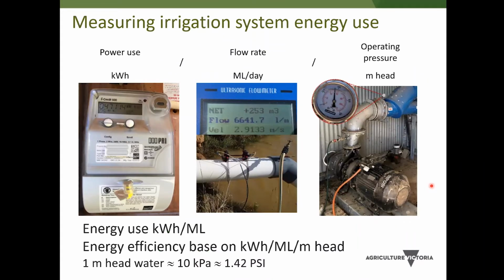Measuring the energy use of a pumping system is actually pretty easy. Most people could easily do it. All we need to do is measure power consumption or diesel consumption over the same time as we measure the amount of water applied. So we need a dedicated power meter. So make sure that there aren't other appliances or irrigation systems operating off that meter, or if there are, that they're turned off when you're doing the assessment, and take a reading at the start and the end of an irrigation event. Also need a flow meter, which some systems don't have. We have a portable system that we use when we do our assessments, but we just need to know what the flow rate is during that irrigation so that we can work out how much water is applied. And that gives us energy consumption in kilowatt hours per megalitre of water pumped.